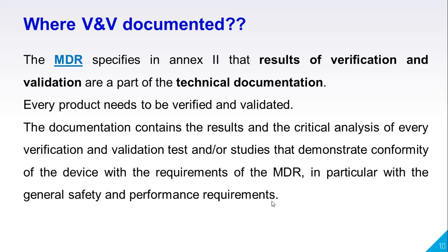As per GSPR, there is one rule, GSPR. GSPR means general safety and performance requirements. As per GSPR also, these verification and validation results you have to include in the STED, that is the technical documentation in Annex 2. So that is very much important. That is the answer for where V&V is documented.